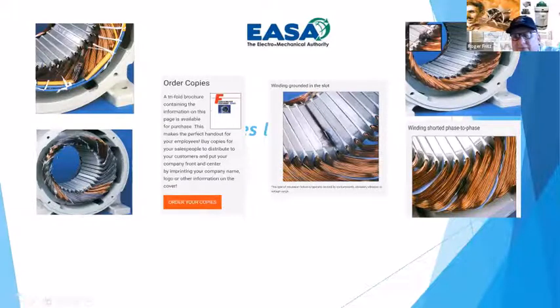This shows a slot failure, and this can happen for various reasons, whether the motor's been rubbing and actually causing damage to the slot insulation. Again, my dad had me sticking windings and coils in motors like this back when I was 10. So I played with them a long time. This up here shows a slot failure where the voltage got too high, or contamination got in and deteriorated that insulation, in this slot. And so it ended up shorting to ground, and you had a ground fault in the motor.